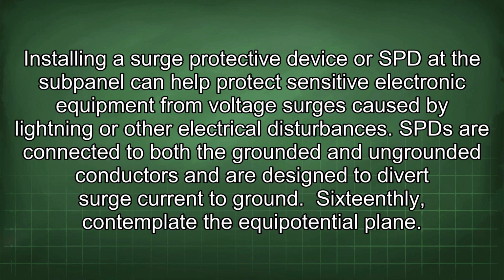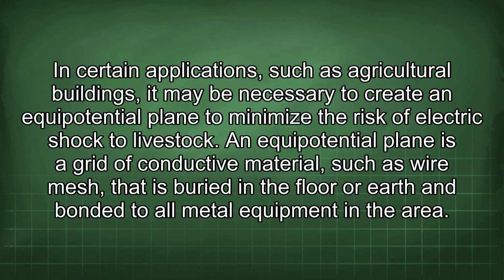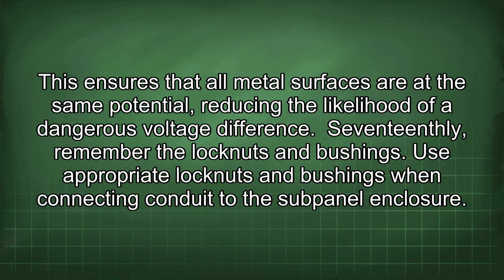16thly, contemplate the equipotential plane. In certain applications, such as agricultural buildings, it may be necessary to create an equipotential plane to minimize the risk of electric shock to livestock. An equipotential plane is a grid of conductive material, such as wire mesh, that is buried in the floor or earth and bonded to all metal equipment in the area. This ensures that all metal surfaces are at the same potential, reducing the likelihood of a dangerous voltage difference.